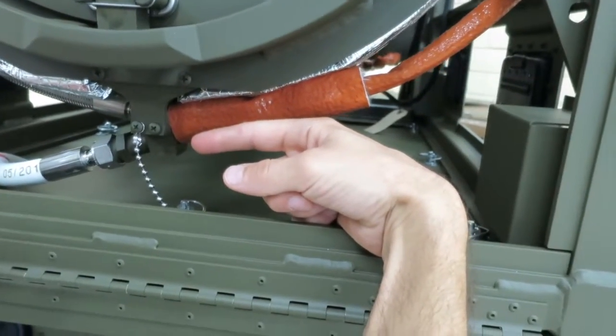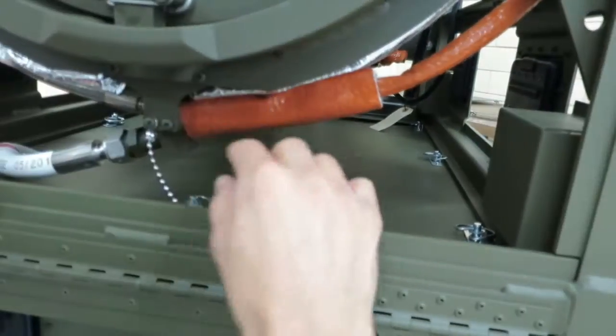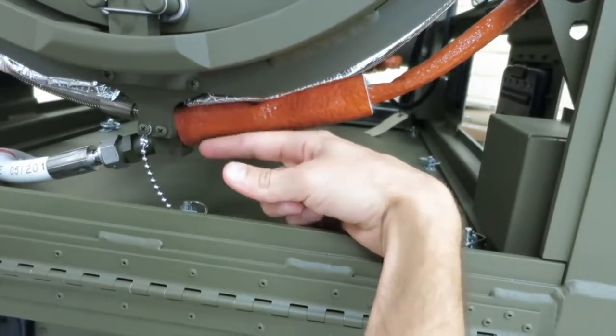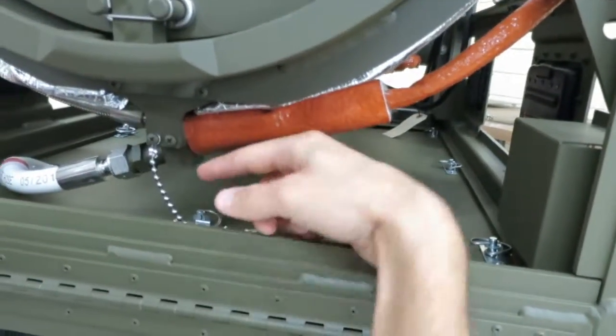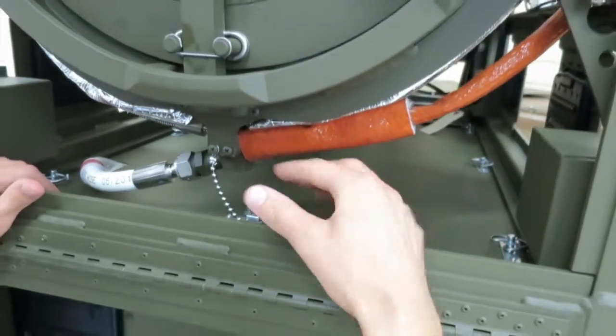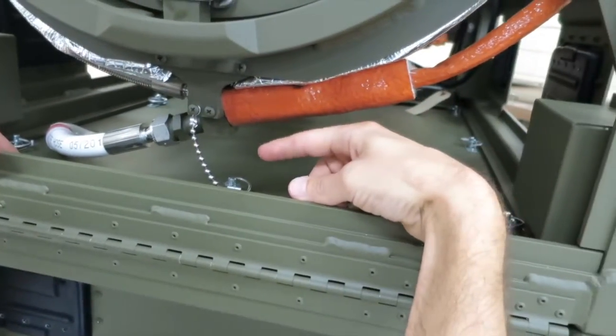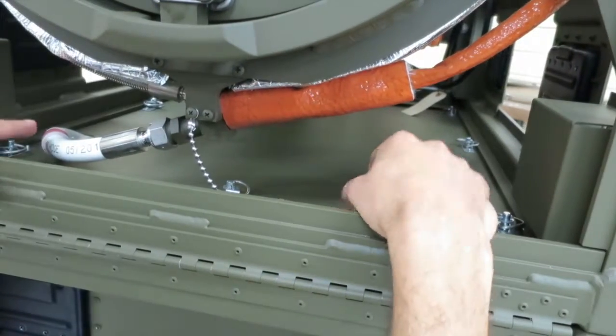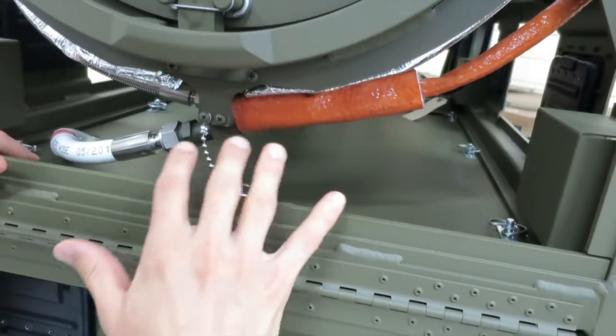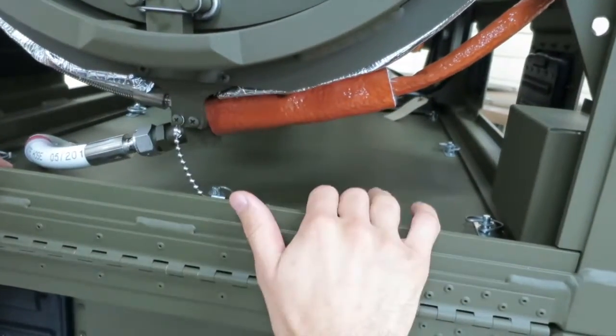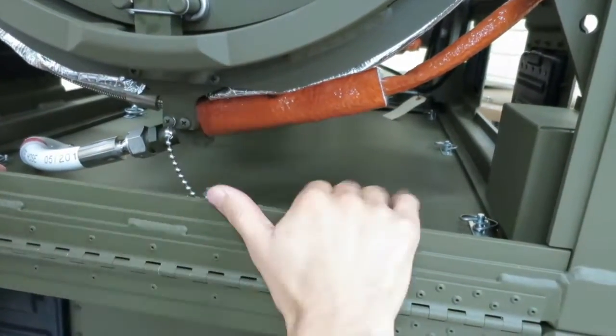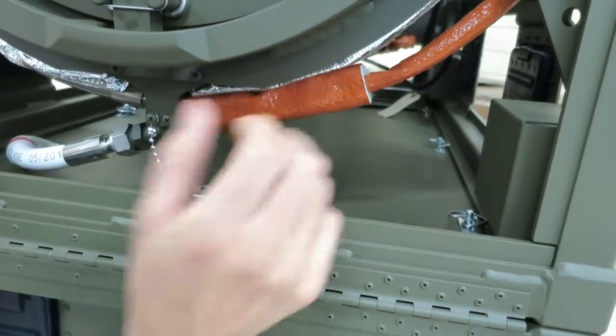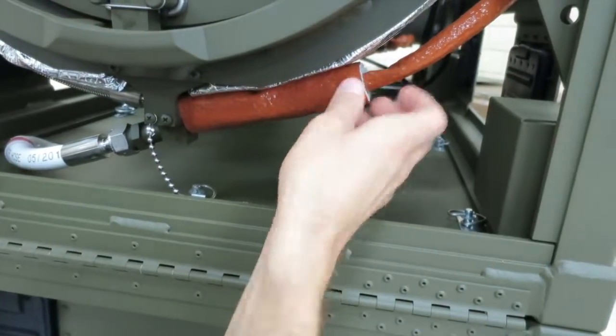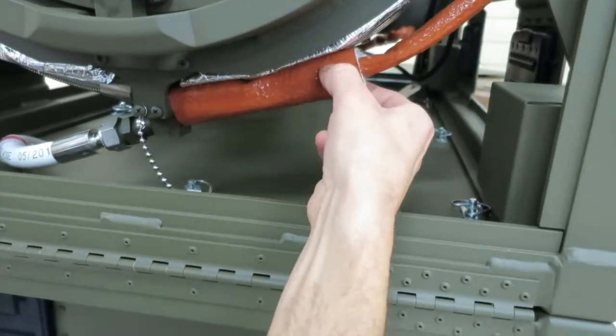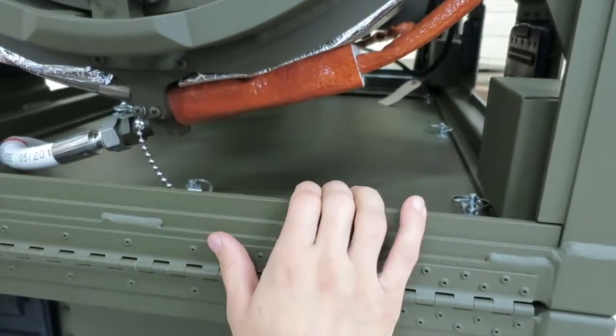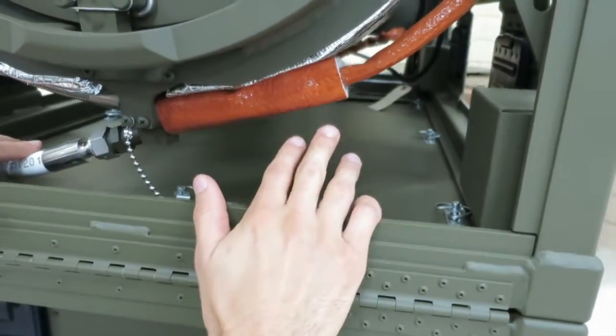The reason we have two is it controls off element 1. So as the sterilizer is running and holding temperature, it's reading off of 1. The second element is for a double check. The second element is always checking up on 1 to ensure that it's reading the correct temperature and that it's not damaged. That way you know that the chamber is at the correct temperature during your exposure and you're killing all your bacteria. To replace this, we have a procedure, but you pull this large insulation this way and you'll see a Swagelok nut that you can break and pull out the whole probe. And that's it for the front.